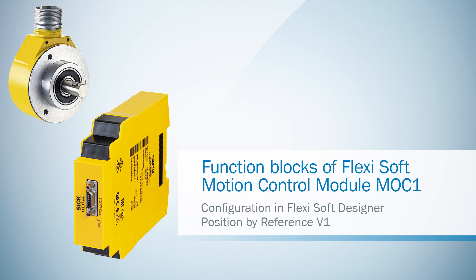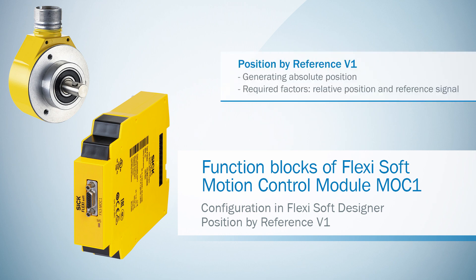This function block is used for generating an absolute position. Therefore two different factors are required: a relative position which comes for example from a sine-cosine incremental encoder, and a reference signal which is triggered for example by using a reference switch.